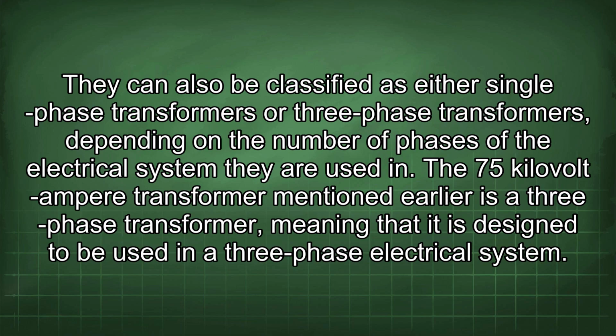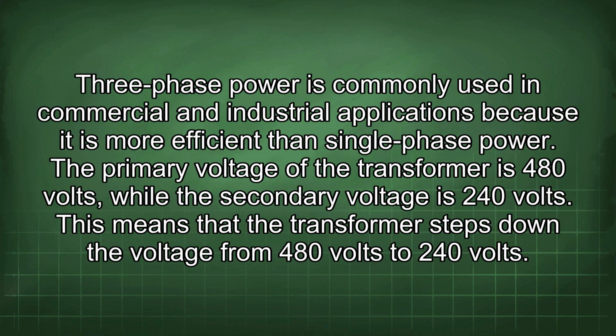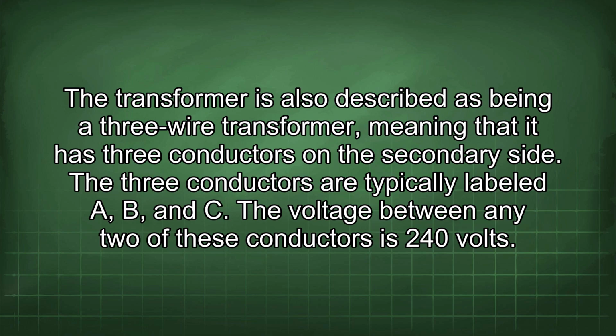The 75 kVA transformer mentioned earlier is a three-phase transformer, meaning that it is designed to be used in a three-phase electrical system. Three-phase power is commonly used in commercial and industrial applications because it is more efficient than single-phase power. The primary voltage of the transformer is 480 volts, while the secondary voltage is 240 volts. This means that the transformer steps down the voltage from 480 volts to 240 volts. The transformer is also described as being a three-wire transformer, meaning that it has three conductors on the secondary side. The three conductors are typically labeled A, B, and C. The voltage between any two of these conductors is 240 volts.